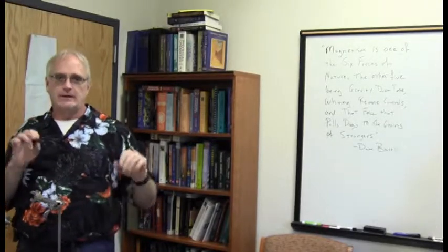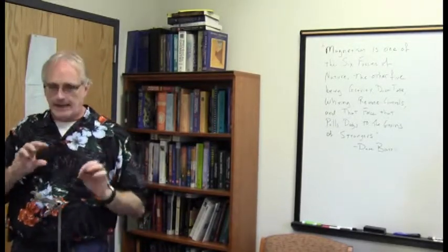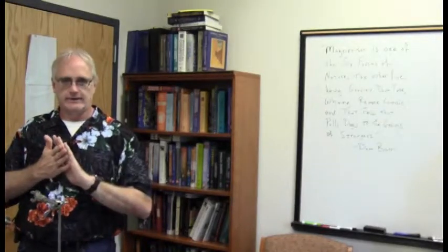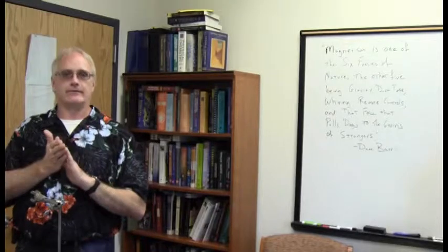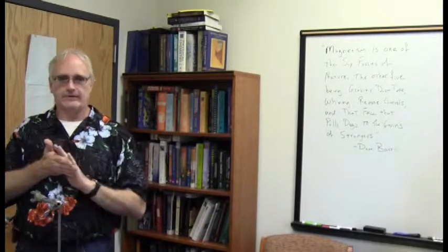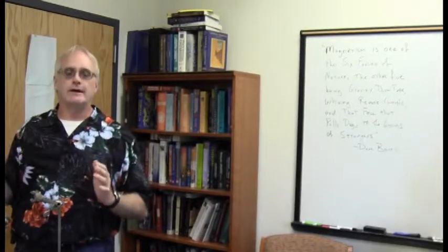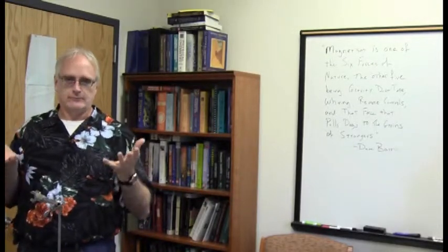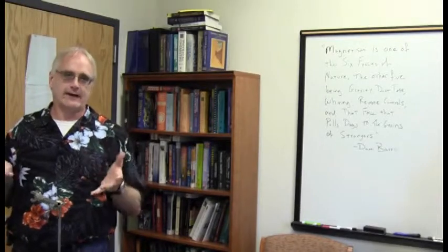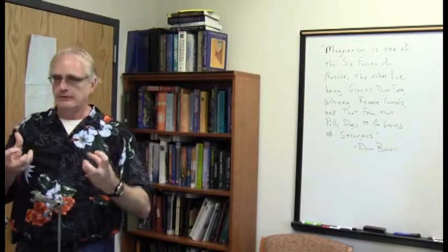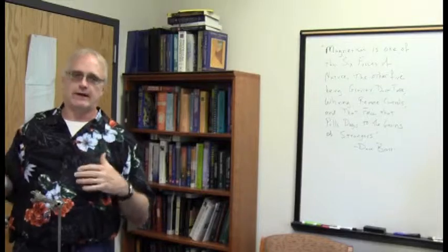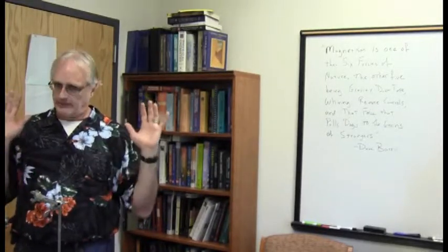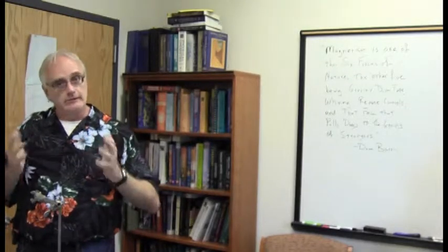And so we listen to the FID, it decays, and then we do it again and add the two results together. Do it again, add that result in, do it again, add that result in, and keep doing this for a number of cycles until we get a set of raw data, the FID, that contains all the spectral information. It's much like that pile of radio frequencies, that pile of radio stations. It's a mess to look at. Here's what it looks like.